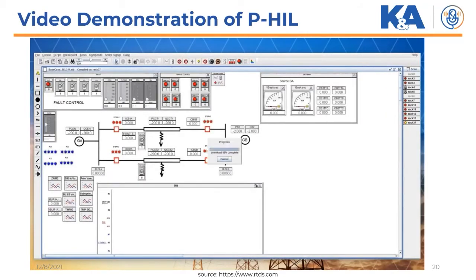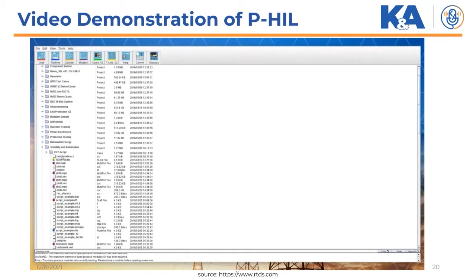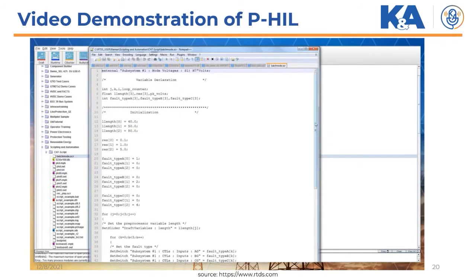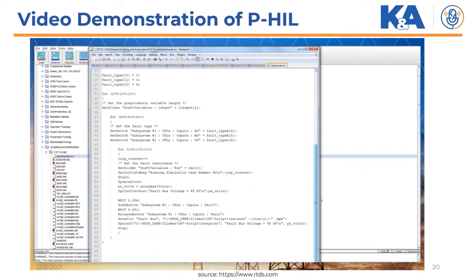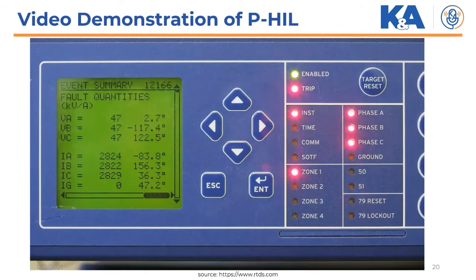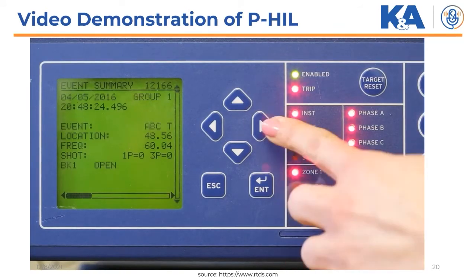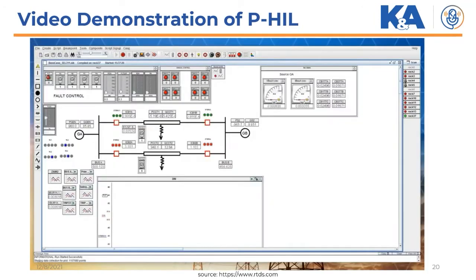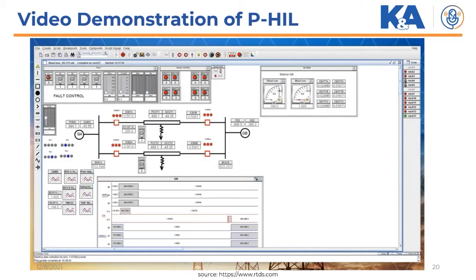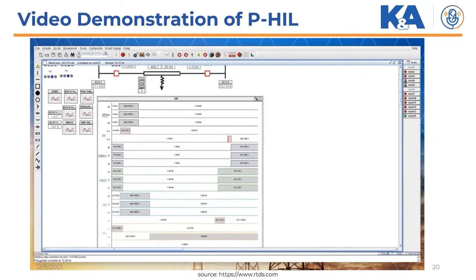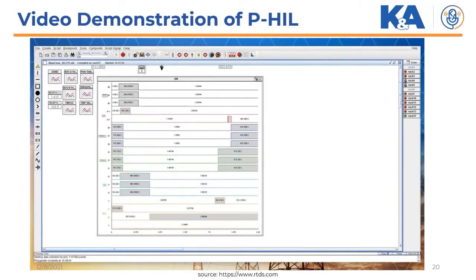From the runtime module, the user can adjust which phases are faulted, as well as the fault's position on the line and the duration, resistance, and fault inception angle. When ready, the user can press the push button to activate their fault. The user can automate this process by generating a script file for batch mode testing and report generation for hundreds or thousands of test cases. After the fault is triggered, an inspection of the physical relay shows the expected response. In the software, we see the circuit breakers open accordingly, and we can view data describing the system's response before, during, and following the fault.